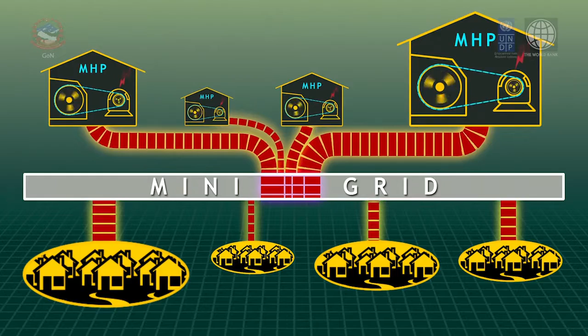Droop CT as a part of the automatic voltage regulator helps to share the reactive power in same proportion to the capacity of the generator. That means bigger microhydro plants get bigger load share and the smaller ones get smaller shares.